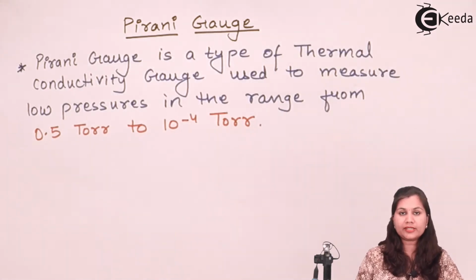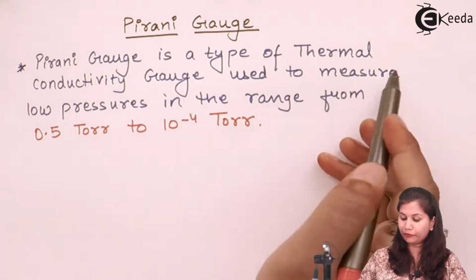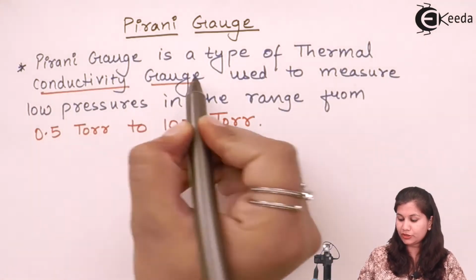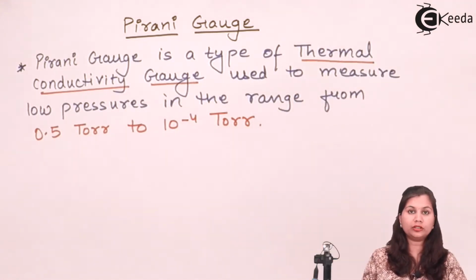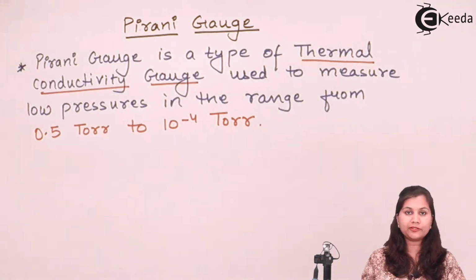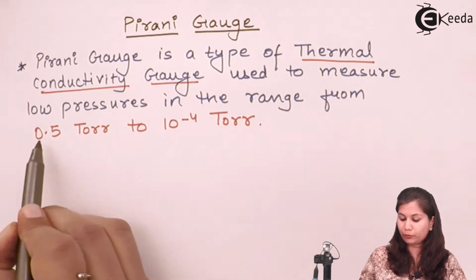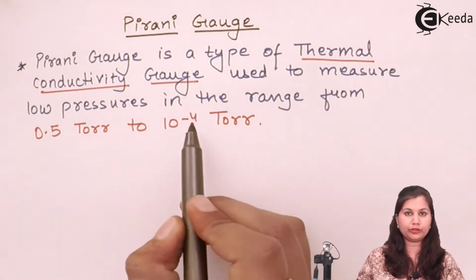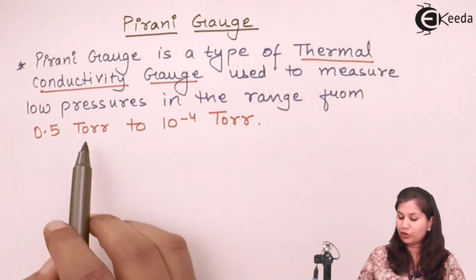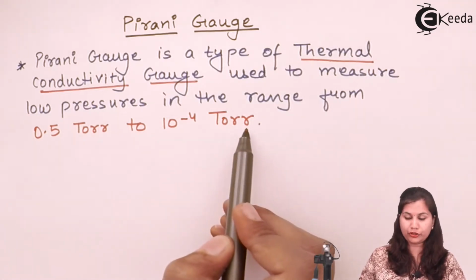So Pirani gauges, they are based on the principle of thermal conductivity. So they are a type of thermal conductivity gauge and they are used to measure the low pressures like the vacuum and the pressures which are in the range from 0.5 torr to 10 raised to the power minus 4 torr. Torr is the unit of the pressures.